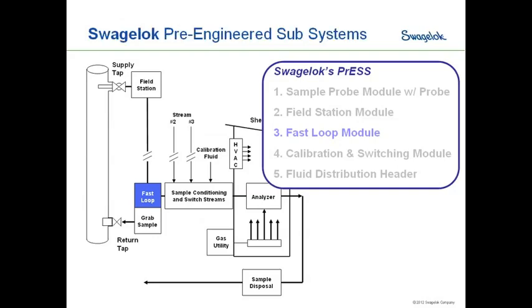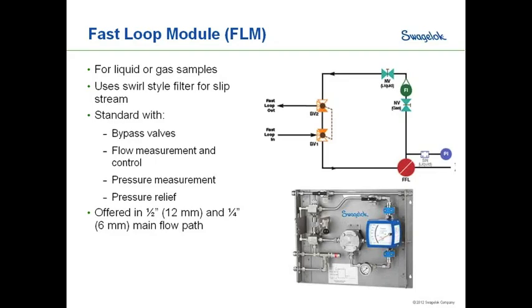The third unit is the fast loop module, which is quite an interesting one. Fast loops are used mainly with liquid samples, because liquid samples must be taken and returned to the process, though gas samples also sometimes use fast loops. For this reason, we produce two versions: a half-inch version for higher liquid flows and heavier liquids, and a quarter-inch version suitable for lighter liquids and gases.